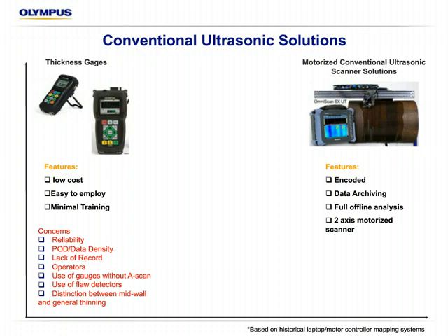Within limit, it's not something you can't do, but today's high-quality thickness gauges do have a lot of algorithms, special features, and measuring modes that will give you the best results in actually getting a thickness measurement versus most flaw detectors.